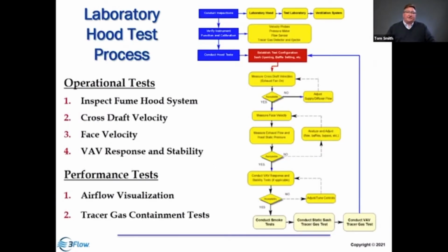So we have a process. This process starts with an inspection. We want to inspect the lab hood, the lab environment, and the system. Then we move to verifying that all of our test equipment is properly calibrated and functioning. Then we want to conduct our hood tests. We need to evaluate the hood itself and determine the appropriate sash configuration, the baffle settings, and how other set points are manipulated, so that we're testing it under a defined set of conditions.